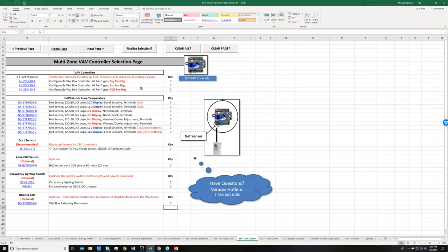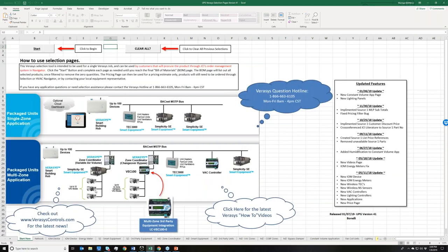Okay, do you have to use shielded wire? No, and that's a good question, I don't think I talked about it. Typically we use for the system bus 22 gauge 3 wire for the communication bus from the smart building hub, because Verasys runs on BACnet MSTP. So every device connected directly to the smart building hub will use 3 wire, and I always recommend using shielded wire. The shield, as everybody typically knows, is to prevent against high voltage interference.